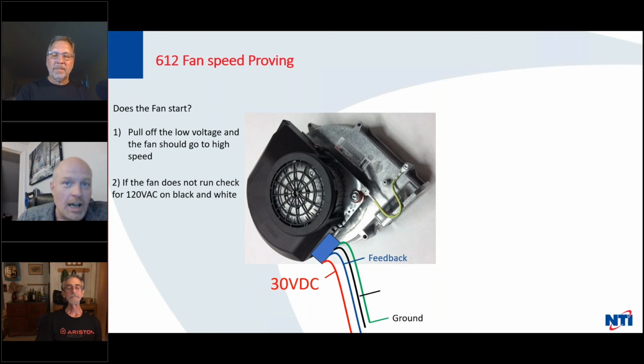The hard one is when the fan appears to work, at least sometimes, and you get intermittent 612s. Now, I will say, in my experience in tech support, 90% of the time, intermittent 612s, especially on the TRX FTVN, it's going to be a fan harness issue. The other 10% of the time, it's probably the fan, and maybe 1 out of 1,000 times is it a boiler control. So, our control is going to fire up. Always, at very least, check for this voltage. So you want to have a look at this harness here. If you see no voltage on any of these wires, and you can just measure each one to ground, and your fan seems to run, like when you remove the low voltage, it could indicate that you have a control problem. It's exceptionally rare, so I almost hesitate to mention it.